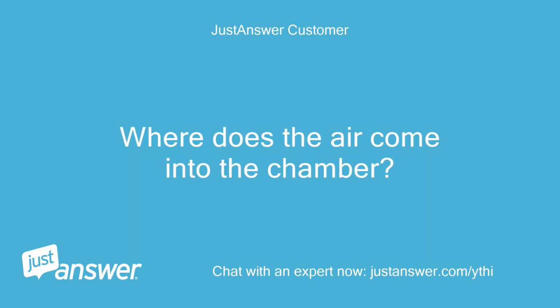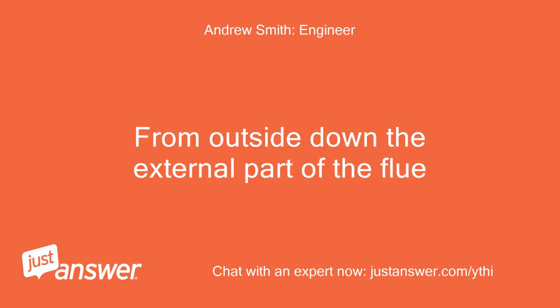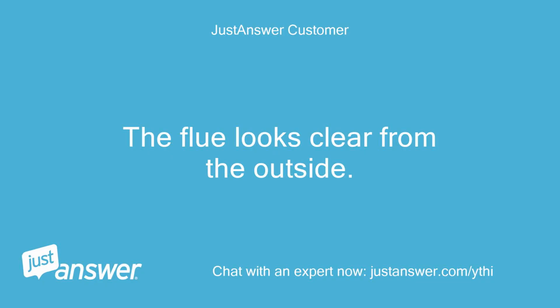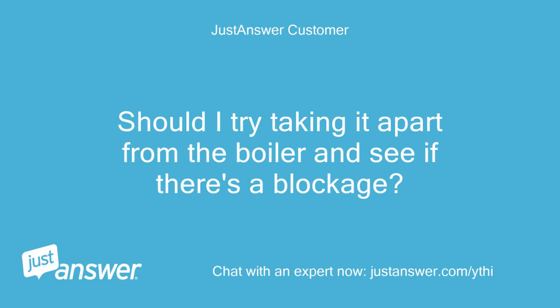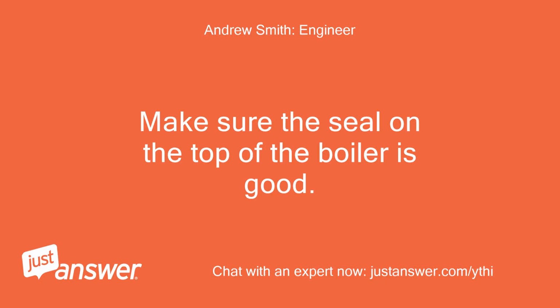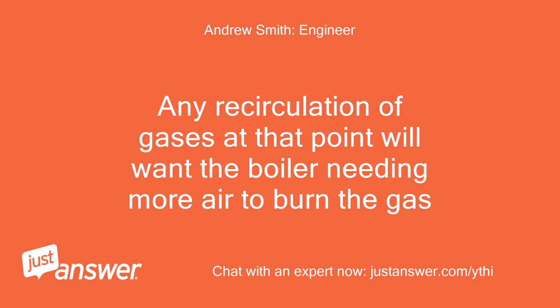Where does the air come into the chamber? From outside, down the external part of the flue. The flue looks clear from the outside. Should I try taking it apart from the boiler and see if there's a blockage? Make sure the seal on the top of the boiler is good. Any recirculation of gases at that point will make the boiler need more air to burn the gas.